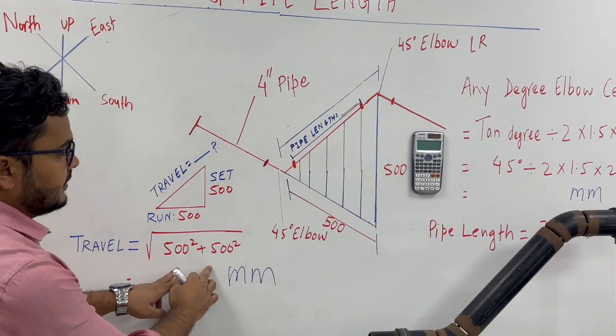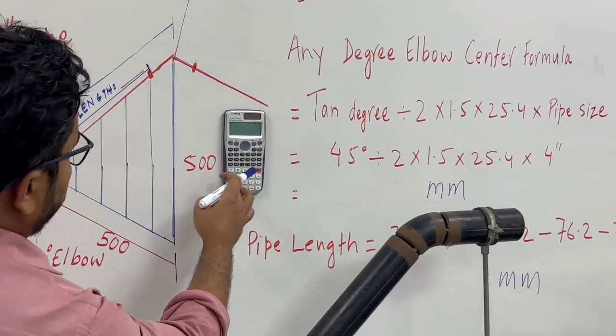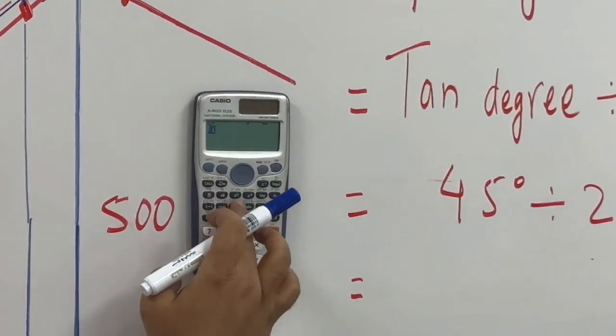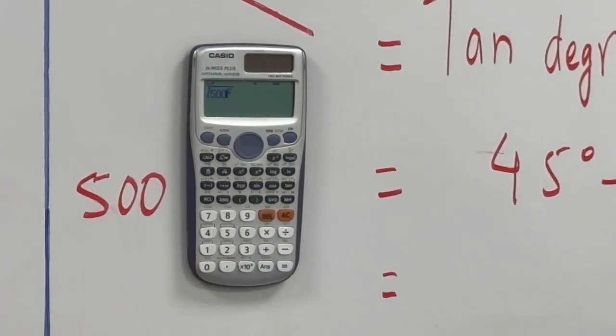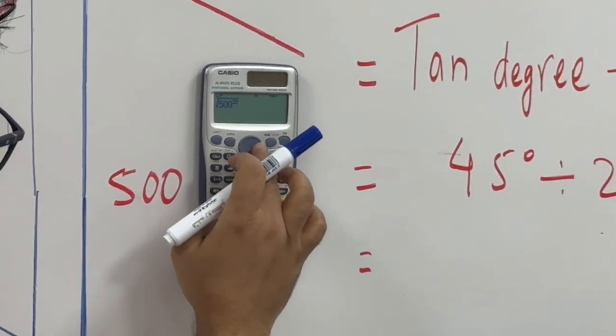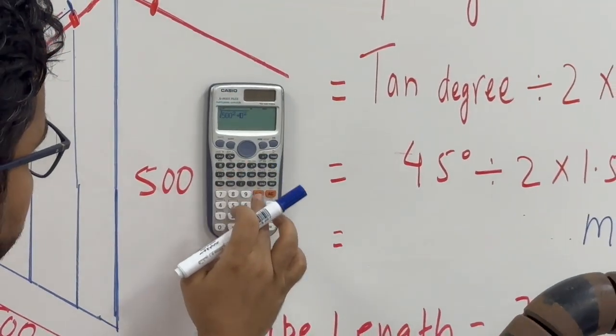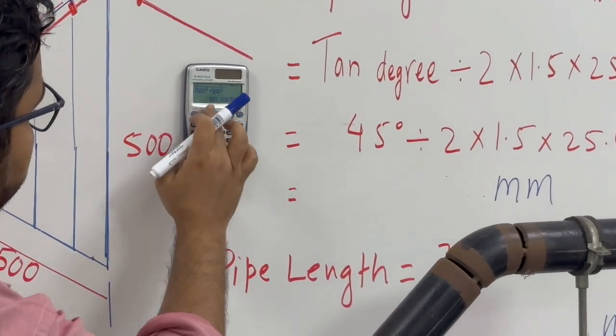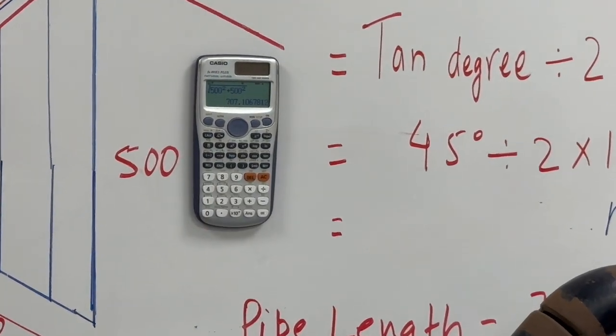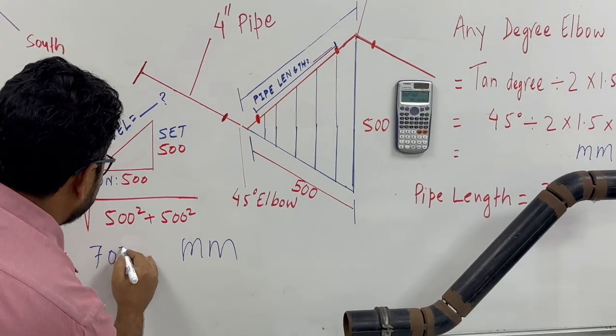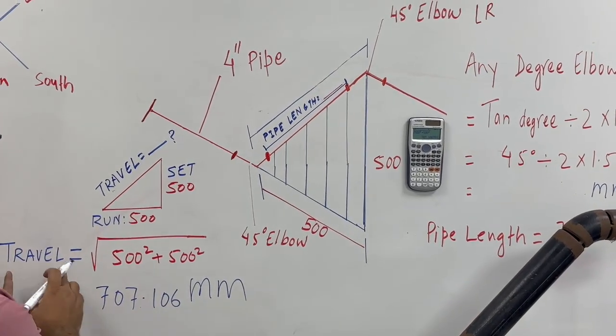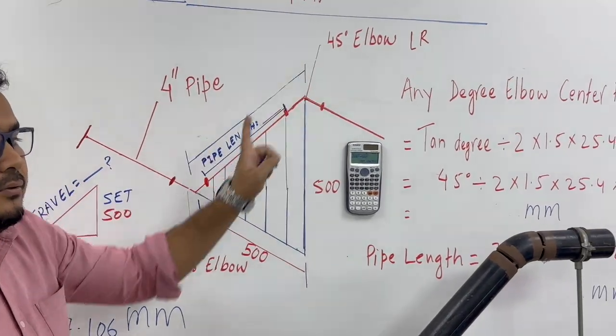Now here we will calculate travel. We have 500 squared plus 500 squared. The square root of 500 squared plus 500 squared equals 707.106 millimeters. So what we calculated is the travel — from this elbow center to this elbow center.